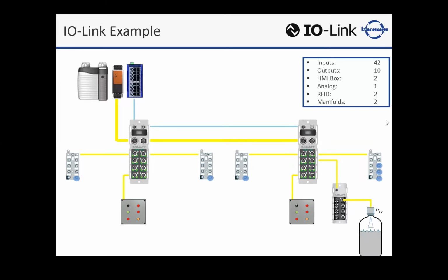We also process analog as well. Yeah, so here's a neat way. We said in networks, IP67 devices were available for analog, but they're pricey. So Balluff designed an 8-port analog master that communicates over to an IO-Link master, consuming 1 port on that master. And that gives you 8 ports of 16-bit resolution analog feedback. Current, voltage, temperature, various models.